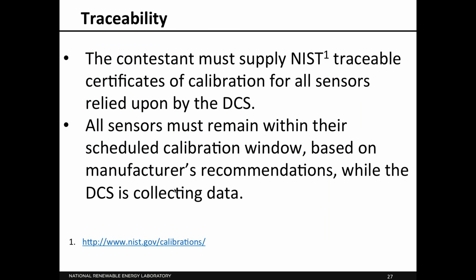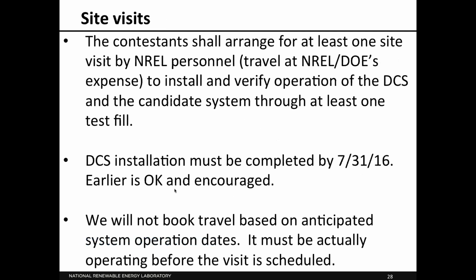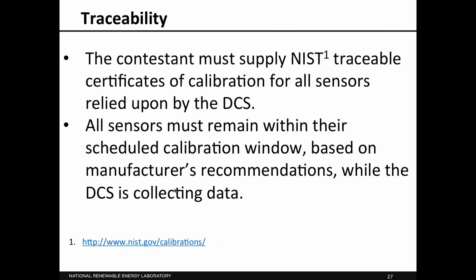So traceability. We will require all of the finalists to supply NIST traceable certificates of calibration for all sensors that the DCS relies upon. Further, the sensors need to be within their OEM's, the manufacturer's, calibration window during the data collection period. If the sensors are not in calibration when we're collecting data, that data won't count toward the 60 days.